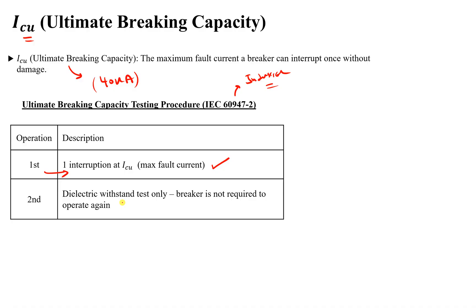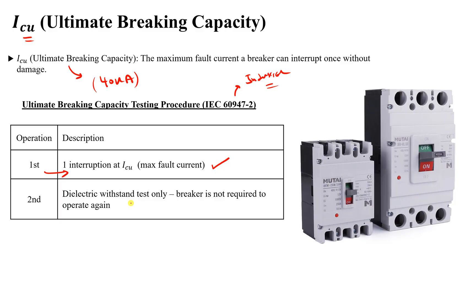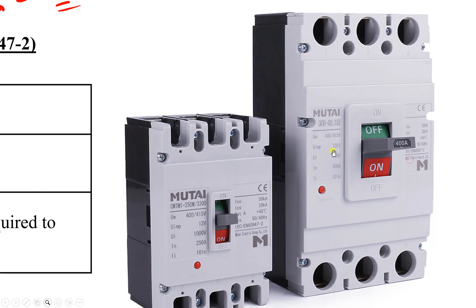The dielectric withstand test ensures that after this severe fault, our insulation level is still the same as before — the breaker's insulation did not degrade. Here is an example: if you look at this circuit breaker, you will see ICU and ICS values, which we will discuss in the next slides.